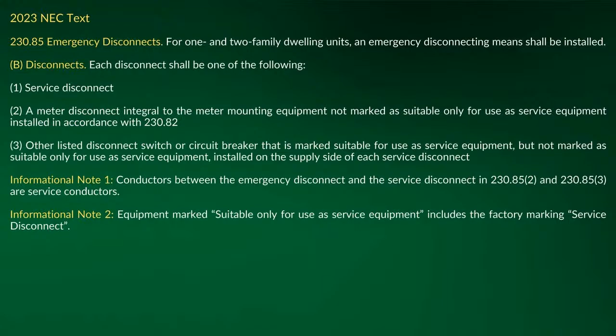Let's hypothetically make another point to this. Let's say that it's not a separately derived system; it's a non-separately derived system. Now, let me go back to this slide here. If you look at that transfer switch there, and I go to a non-separately derived system, look at the way that I'm connecting that. I'm actually using the neutral to connect through the system. But if I go back over here to a separately derived system, the neutral's being switched.